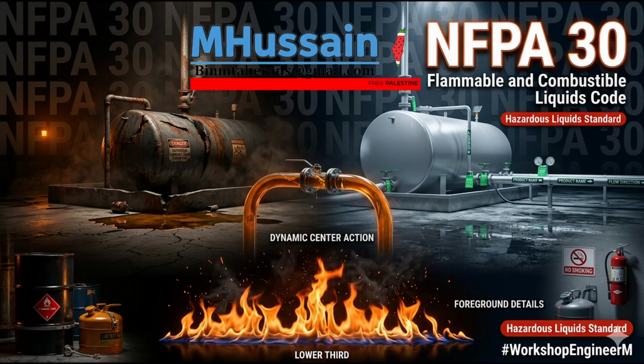Make no mistake, once a Class IB liquid is heated past that 200-degree mark, say, by a smaller trash fire nearby, it becomes a massive fuel load. Massive. It will burn with immense sustained energy. The key takeaway for you, the engineer listening, is that this classification matrix drives literally every single design constraint in your building. You're never just designing a generic liquid storage room. Never. You're designing a space specifically calibrated to the vapor dynamics of a Class IB or a Class IA liquid. It dictates your electrical zoning, like whether you need explosion-proof light switches. It dictates mechanical ventilation. It dictates spill containment.